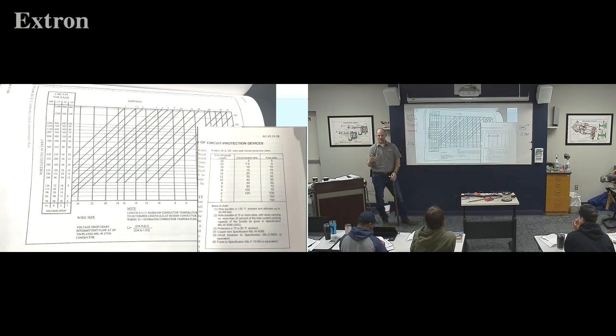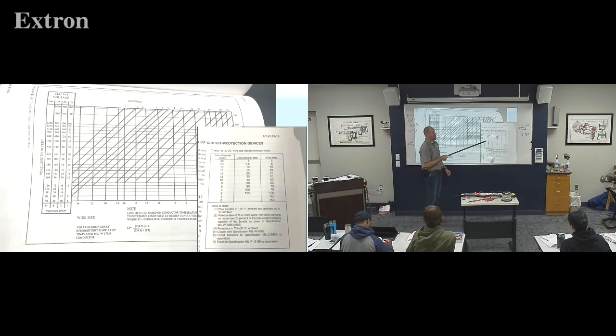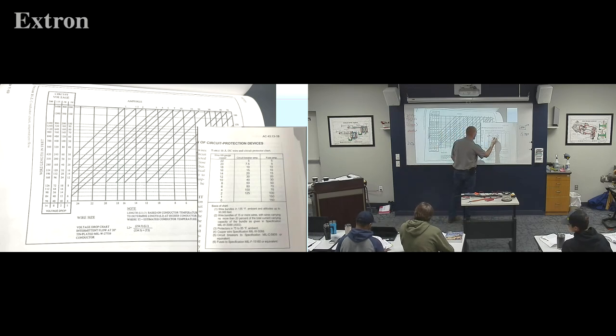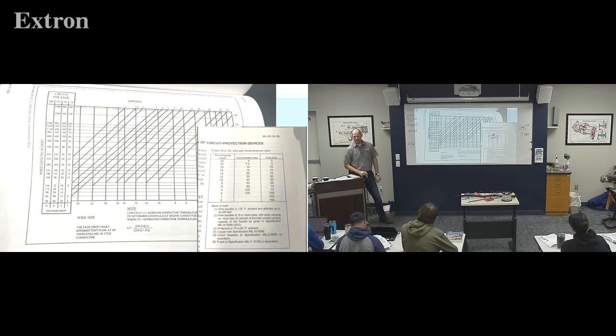So if you want to reverse that, which you're trying to do, which is what we really want to do, you would say, if I have a 20 amp circuit breaker, let's say, so my load's 20 amp, what's the minimum size wire that I could use with that? I got it backwards too. So the minimum size wire, if you're going this way, would be a 14 gauge. So I'll draw that up. Maximum breaker, if you're going to the right, minimum size wire. That'd be a good one to take a picture of.